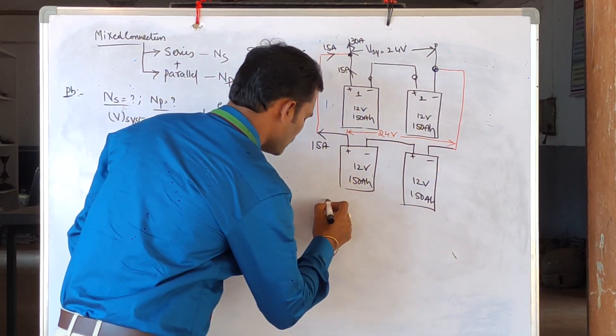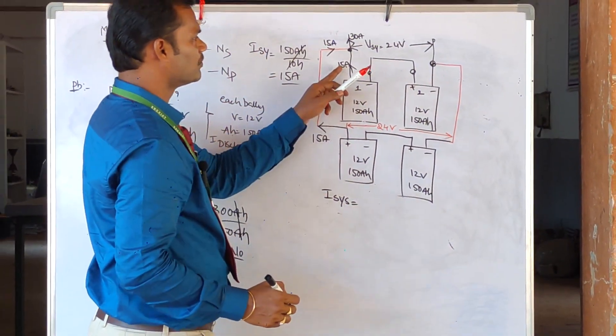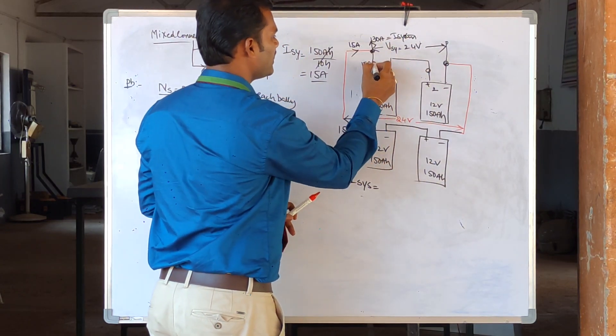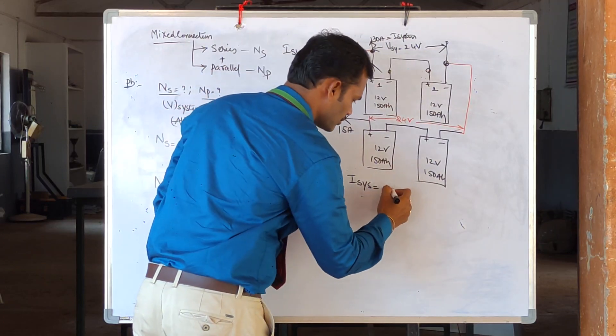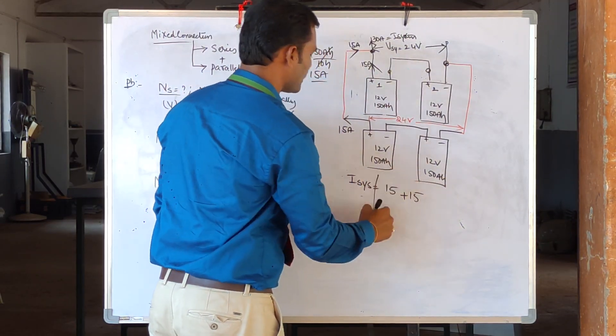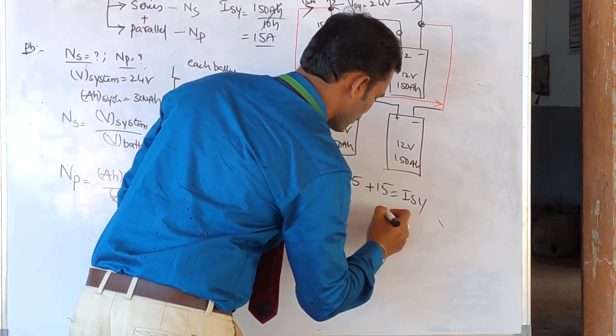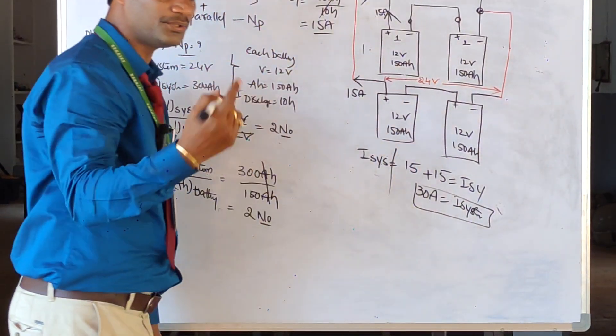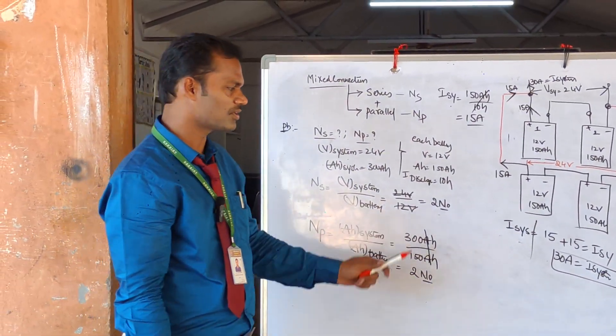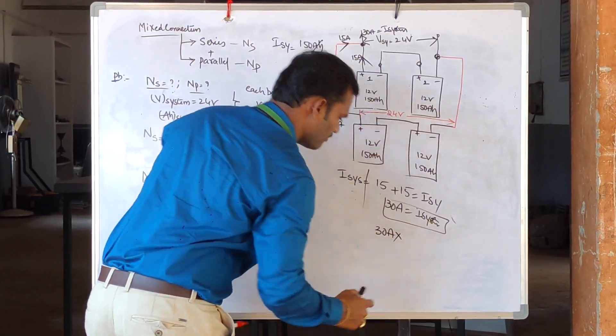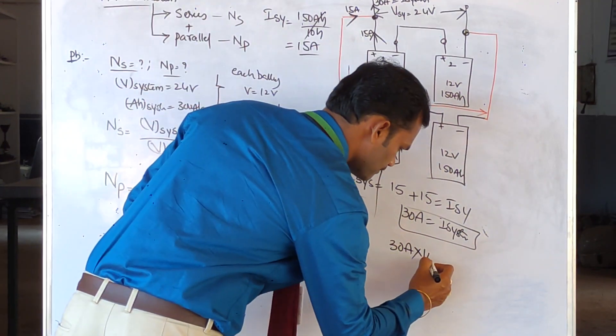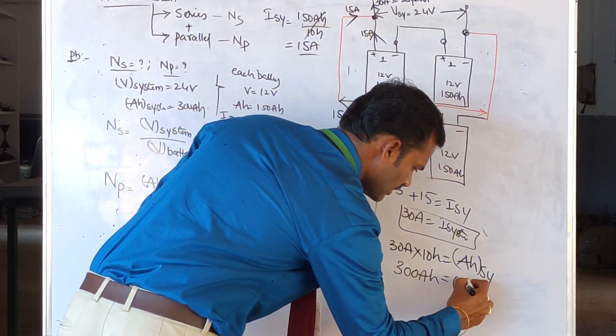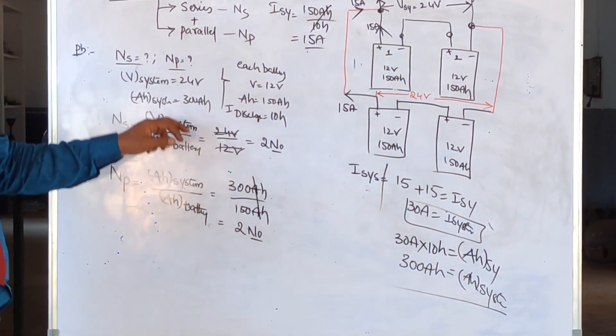Now let's calculate the total AH capacity of the system. System current is 30 Amperes, and we operate for 10 hours. So total AH = 30 Amperes × 10 hours = 300 AH. This matches exactly the AH capacity of the system given in the problem — 300 AH.